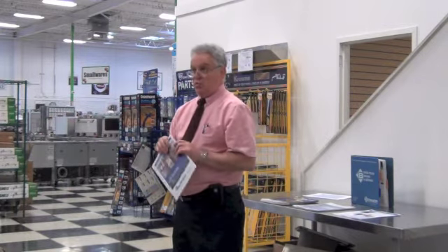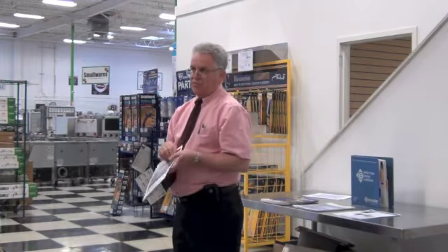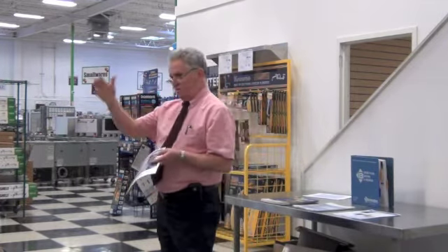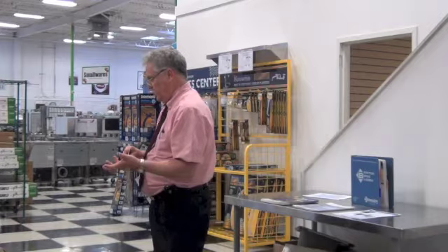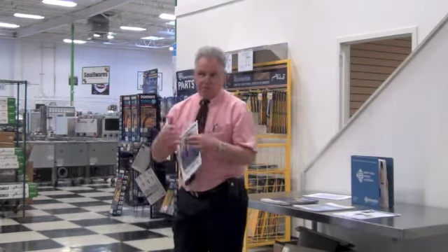On the size of the door, not just the width, you have to know the height as well, because some of these air doors are not designed for above 8 feet. So when you get to a loading dock door, it's 10 feet, 12 feet high, we need to put a different type of unit on. Our standards are 3/4 horsepower. You might need a 1 horsepower. You might need 2 1-horsepowers, depending on the type of door.